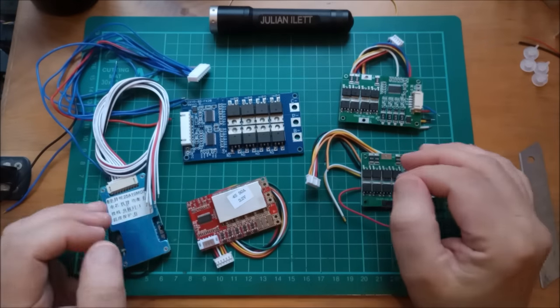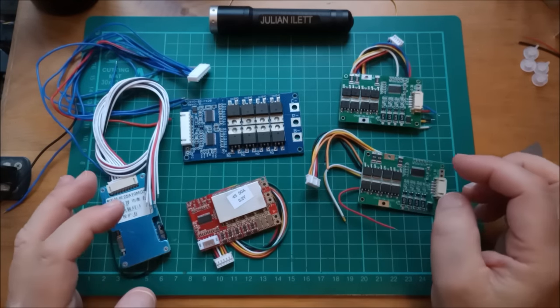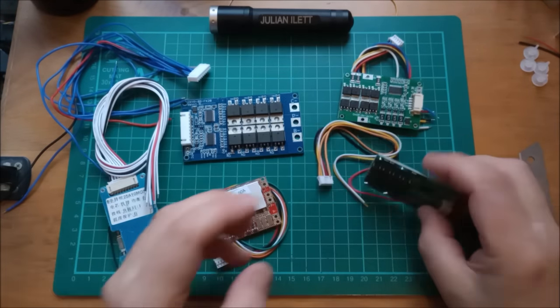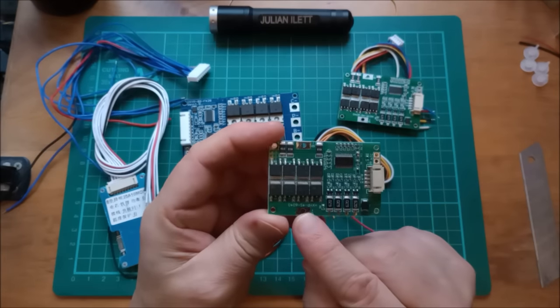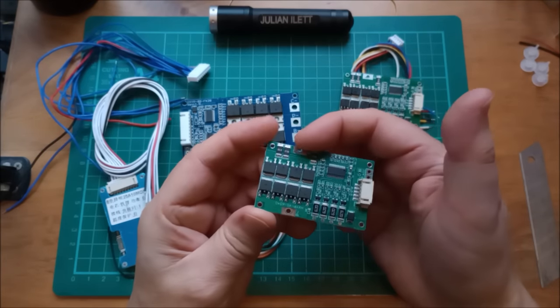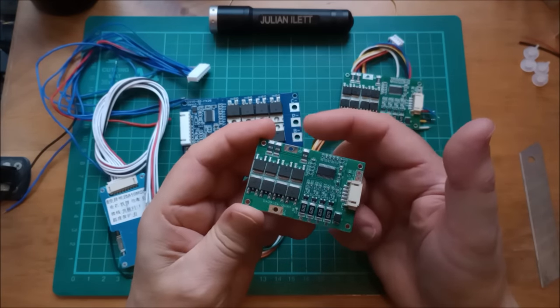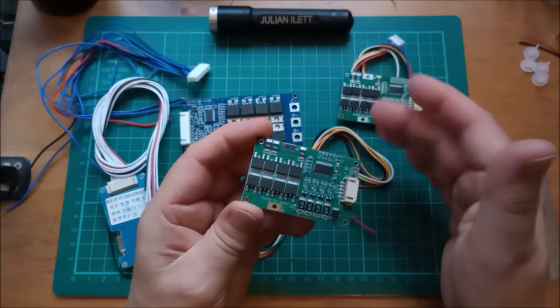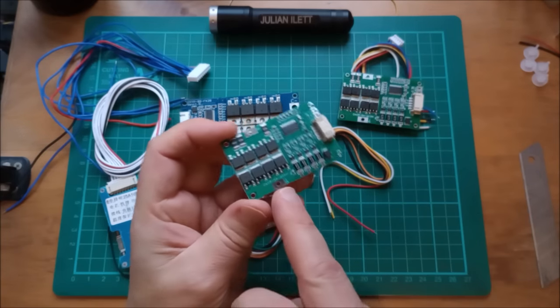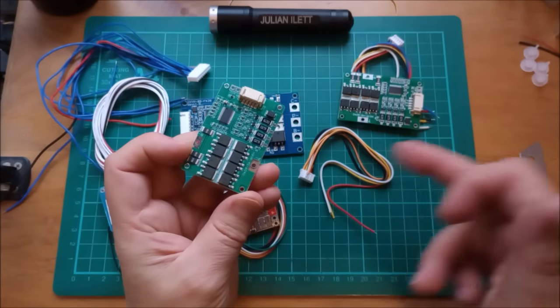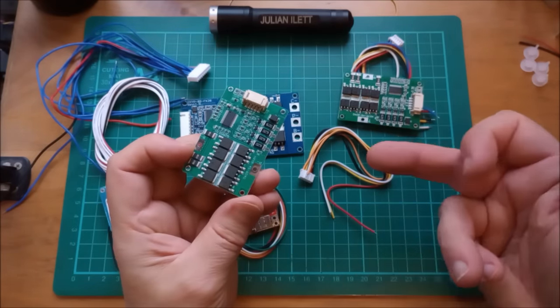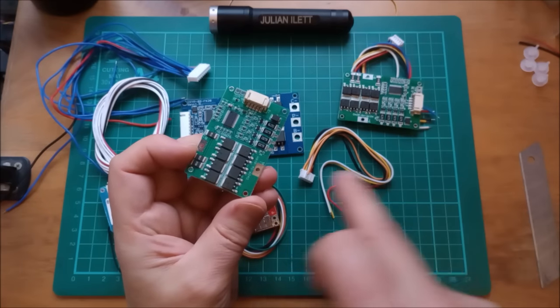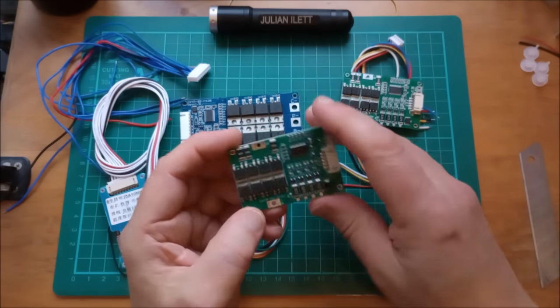Now, I think most of these are what they call common port, where you just have a P minus, that's pack negative, and a B minus. So B minus goes to the most negative point of the battery array, and then P minus is what you use as your outside connection. But you both charge and discharge from that P minus.